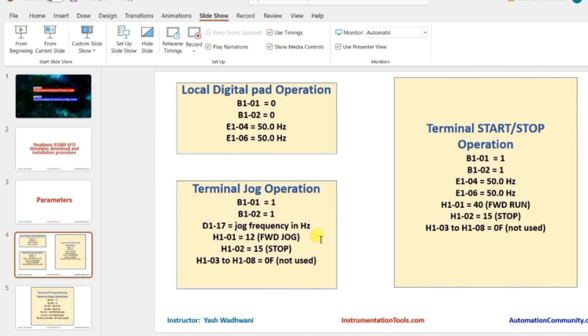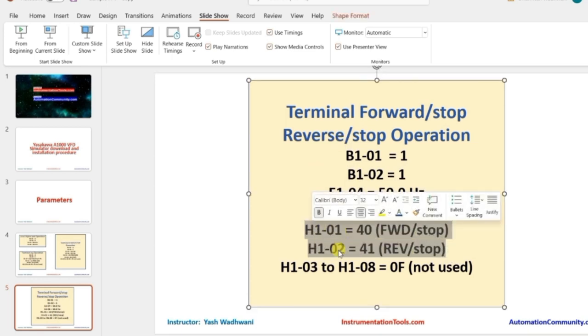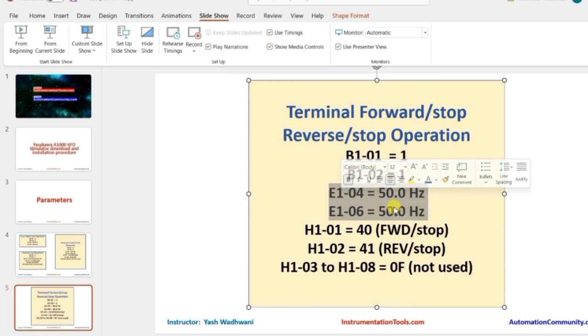Similarly, there are other cases: jog operation, start/stop operation where one button starts and another stops, and forward/reverse operation where one button runs the motor forward and another runs it in reverse. To use this last case, you don't have to change any parameters - by default the software is already in this mode. You only need to change the frequency if you want a specific RPM like 1500.